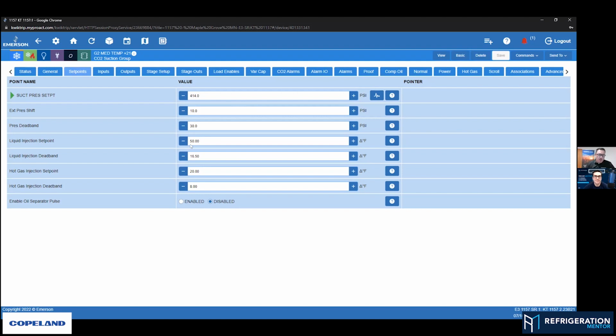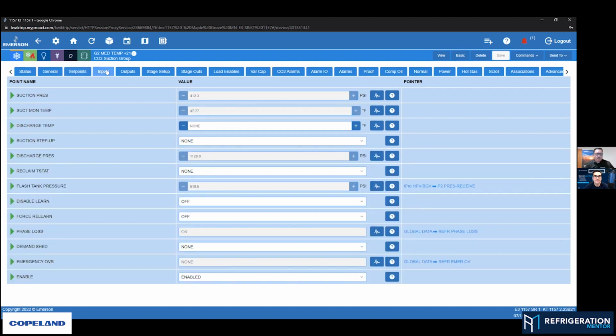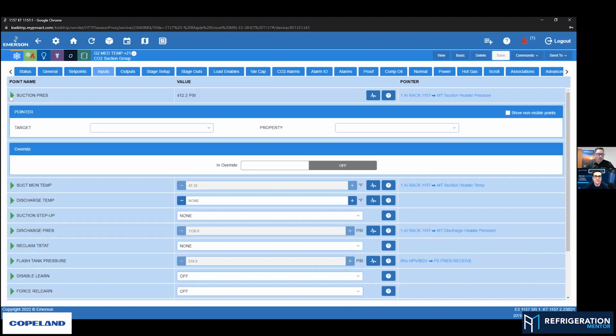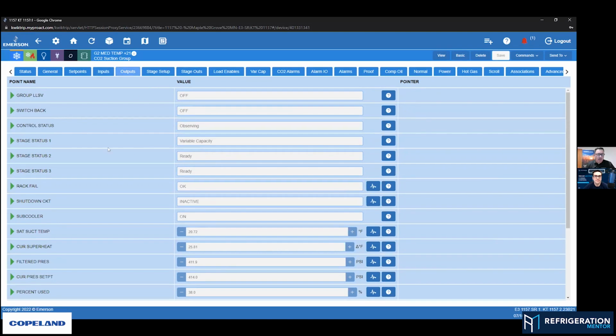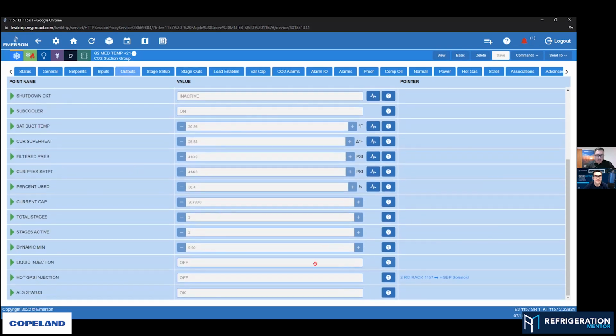And then once you've got those values, you would obviously have to have the inputs, like I was saying here. So we would have to tell it what our suction pressure is. This one is located on one of the input boards for medium temp suction pressure, and then we've got a suction temperature as well. And then we would have to give it an output assignment as well, which in this case is, well, this rack actually doesn't have liquid injection by the looks of it, because there's no output assigned. But we do have hot gas injection, which is the same thing. We're just trying to heat the suction instead of cool down the suction.